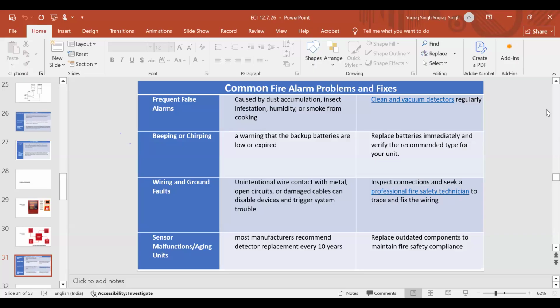What are the problems in this case? The most nuisance is that the fire alarm causes false alarms. Why do these happen? They are caused by dust accumulation. The fire alarm system is actually a neglected facility which keeps giving nuisance problems, but its utility is known when there is a fire. They make sure the fire remains localized. You must have heard about the children studying in a coaching institute who got burnt alive. There, if the alarm is there, they will immediately run before dangerous temperatures are reached.